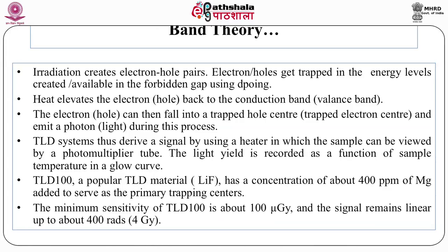There are many TL materials available. TLD-100 is the commercial name of a popular TLD material based on lithium fluoride, with a concentration of about 400 ppm, parts per million, of magnesium added to serve as the primary trapping center. What is the sensitivity of this TLD-100? About 100 microgray, which is quite low.